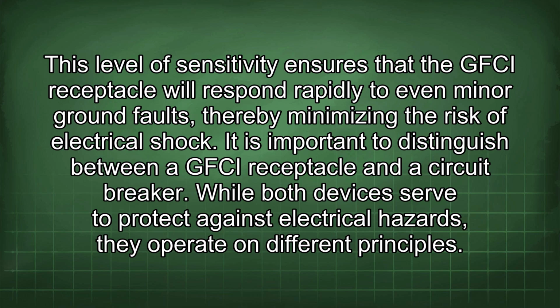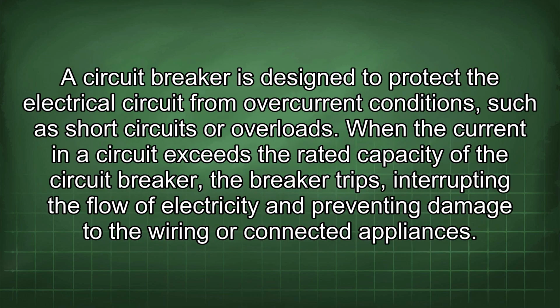It is important to distinguish between a GFCI receptacle and a circuit breaker. While both devices serve to protect against electrical hazards, they operate on different principles. A circuit breaker is designed to protect the electrical circuit from overcurrent conditions such as short circuits or overloads. When the current in a circuit exceeds the rated capacity of the circuit breaker, the breaker trips, interrupting the flow of electricity and preventing damage to the wiring or connected appliances.